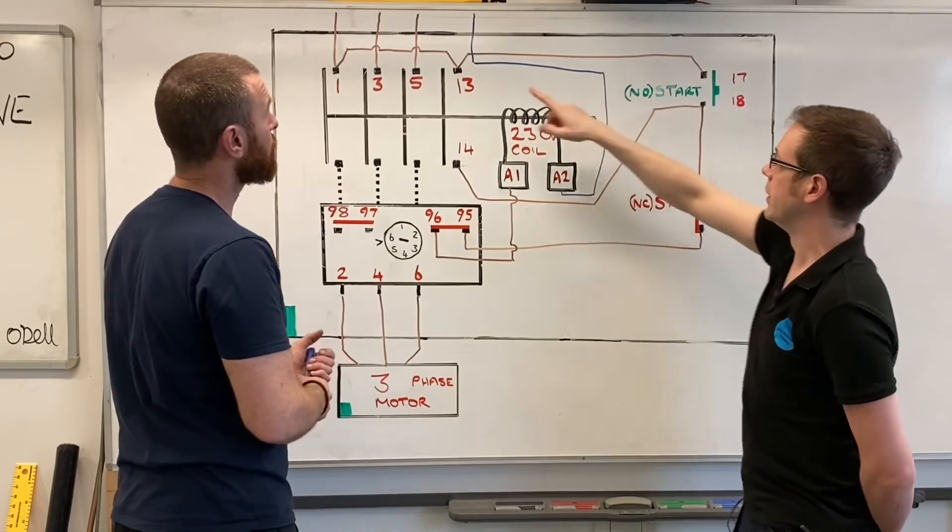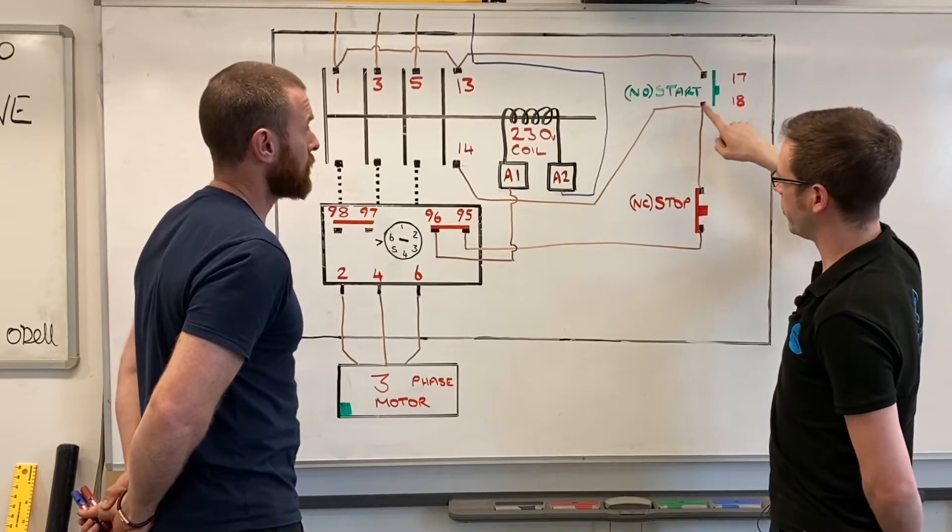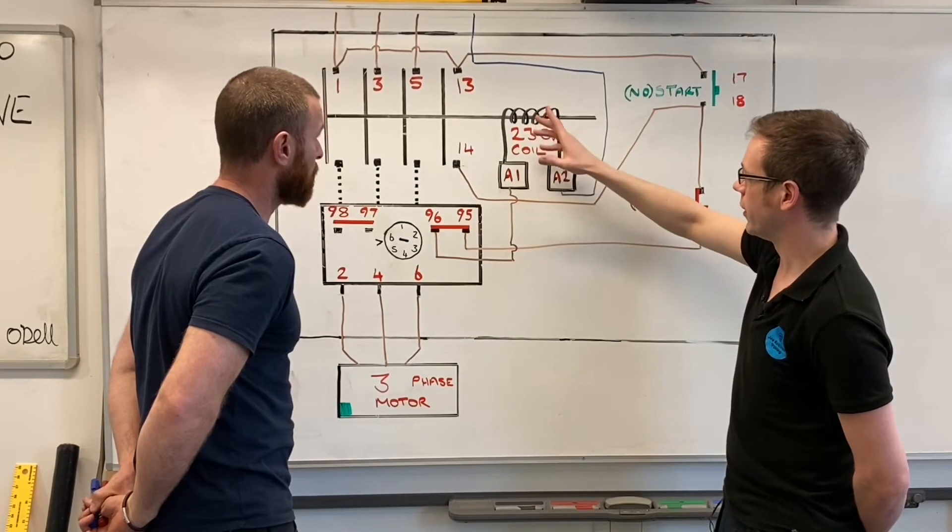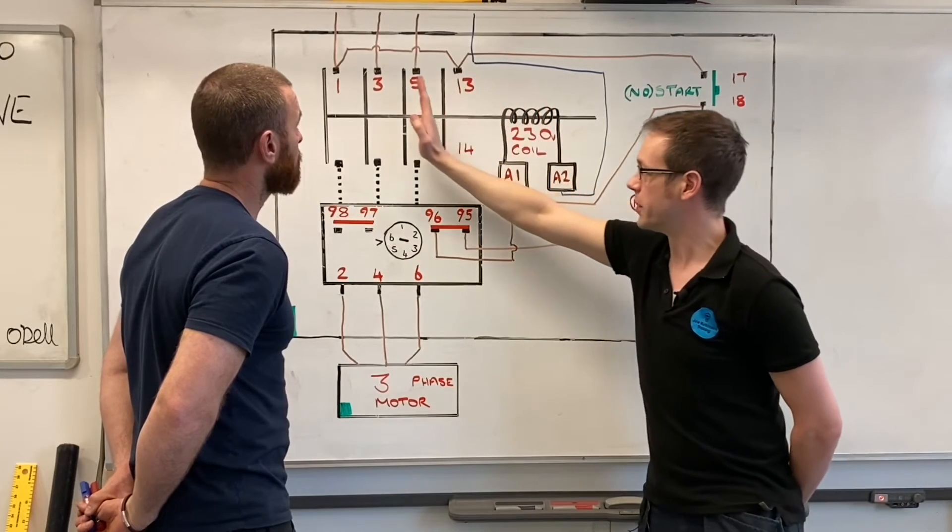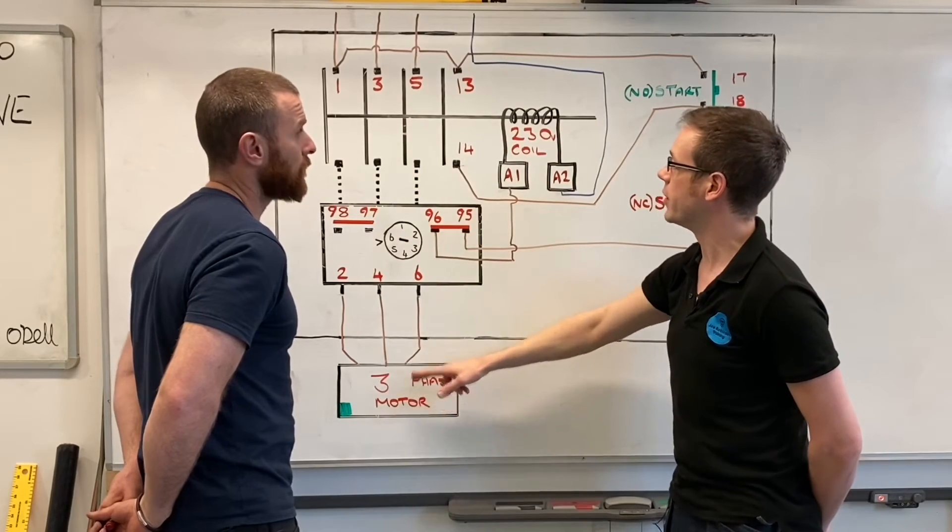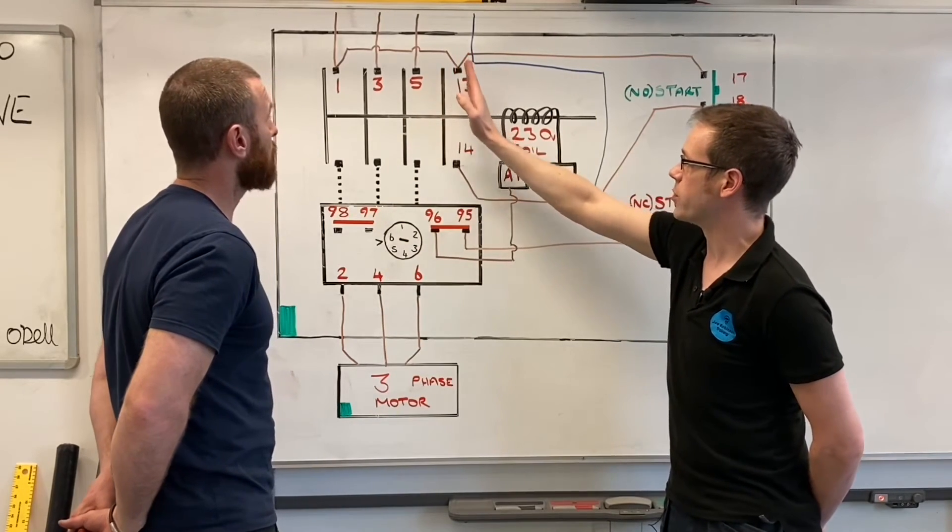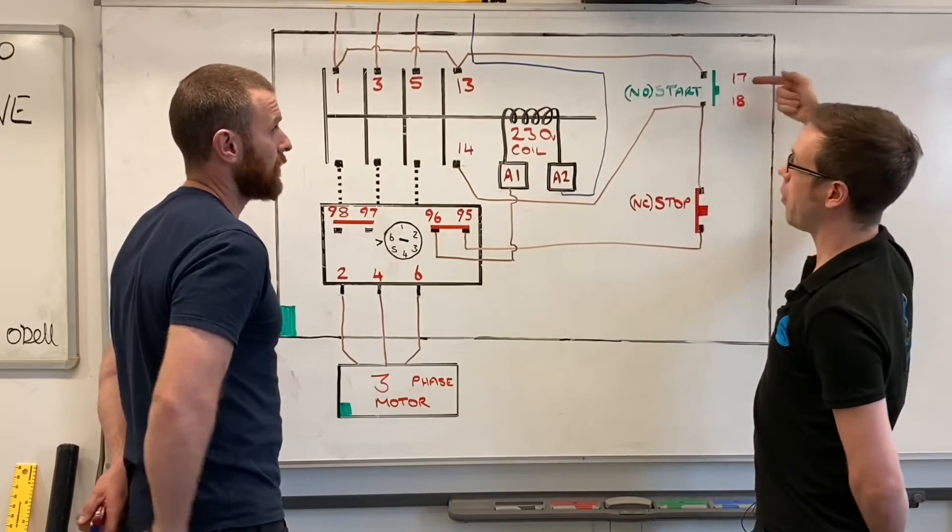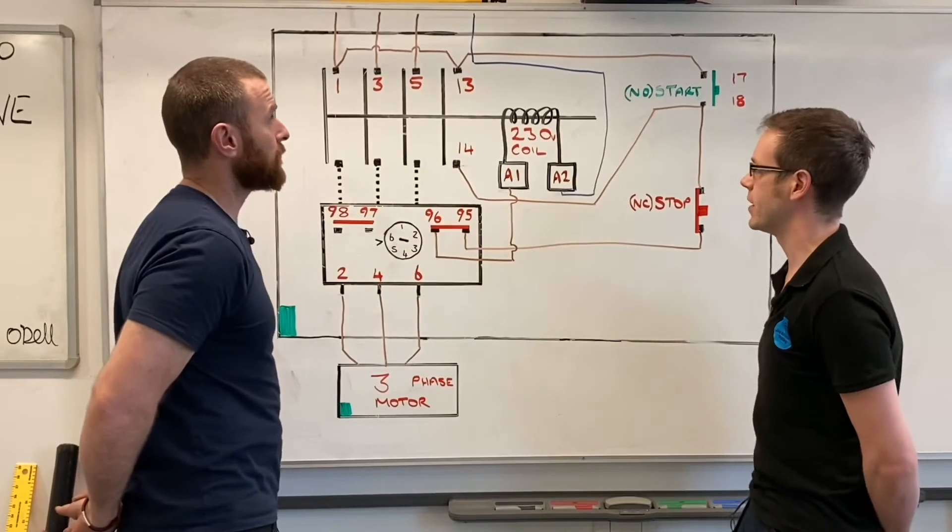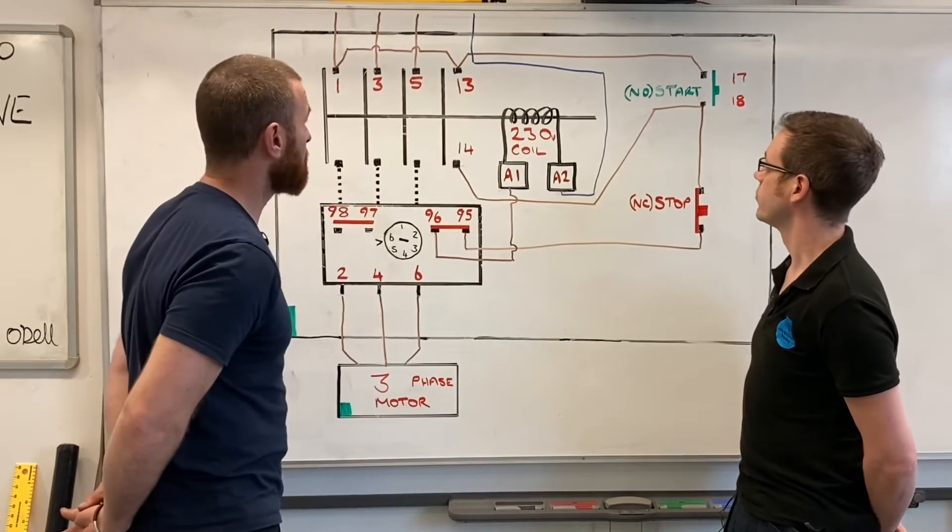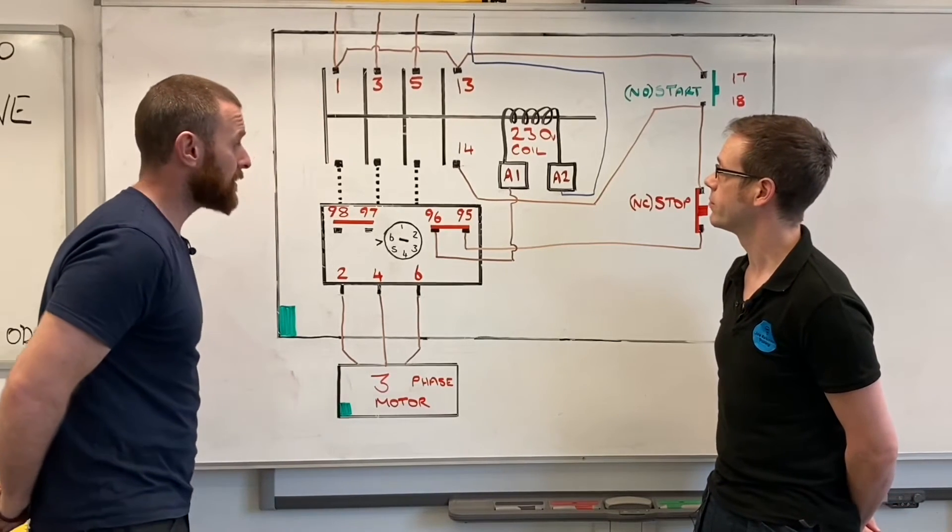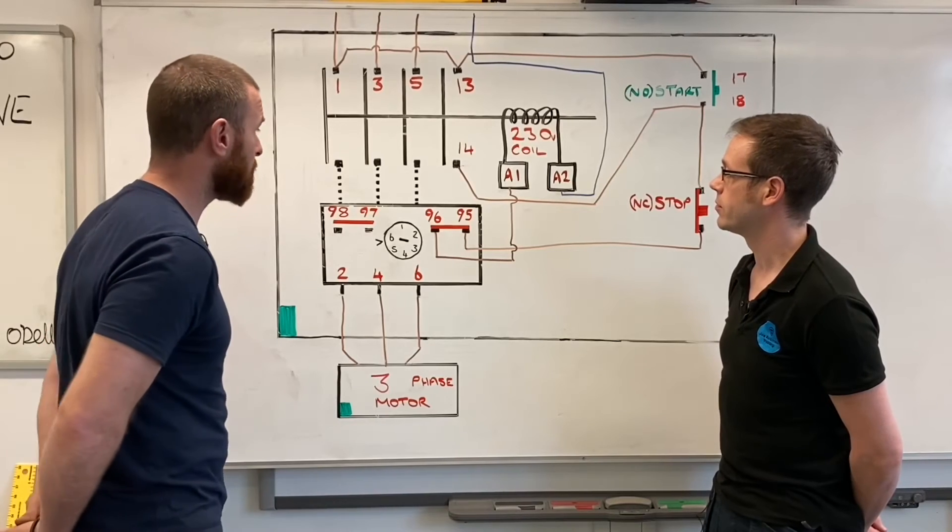We've got that circuit completed and we're seeing that same principle that we saw before. If I press the start button, I create a path that the current can flow through up to A1, bringing my coil in. When the coil comes in, these shoot over making contact not only to the motor which will then be energized, but also between terminals 13 and 14. When I take my finger off the button, current can then flow back through the circuit again, basically bypassing the start button. That's basically the three phase circuit for a direct online starter.